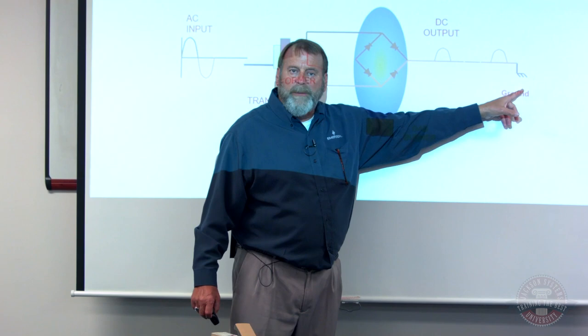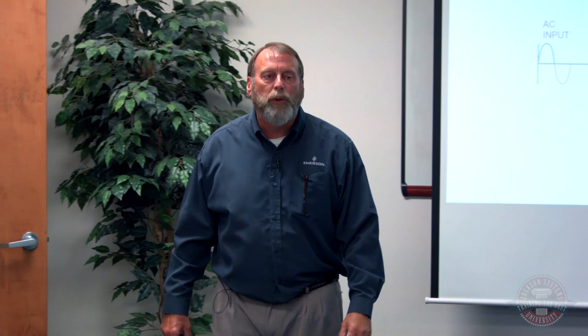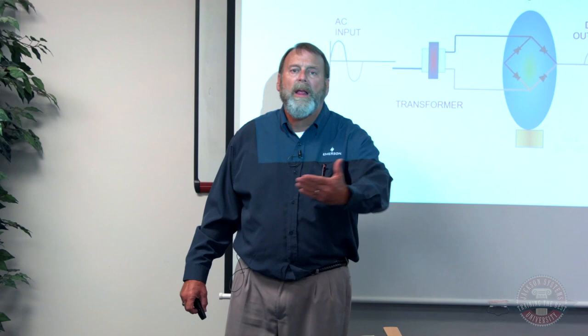Here's your furnace. Inside the vestibule itself, all the metal is the ground. So I'm getting an AC sine wave going through the system and returning to the control. And it returns through the ground plane, which is the burner vestibule, and it eventually goes to the burner manifold. You've got that little green wire on there that goes back to the control. That's your return path for ground.